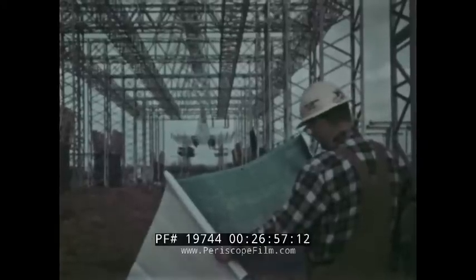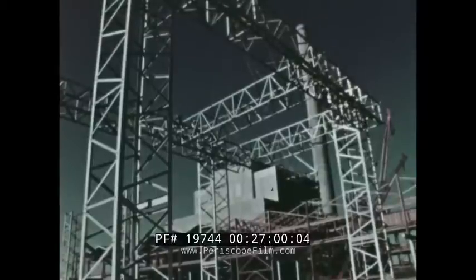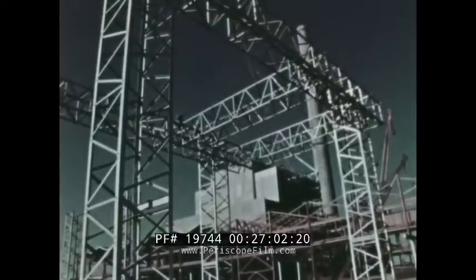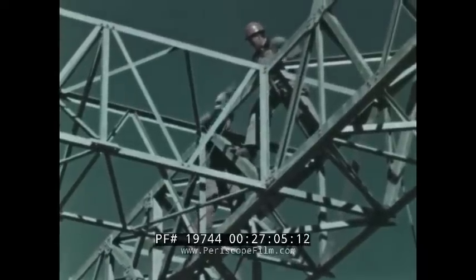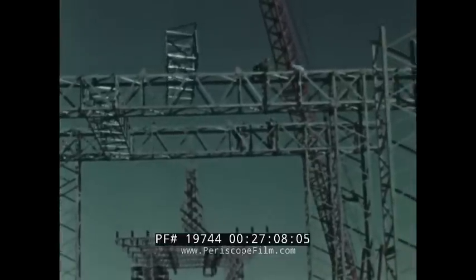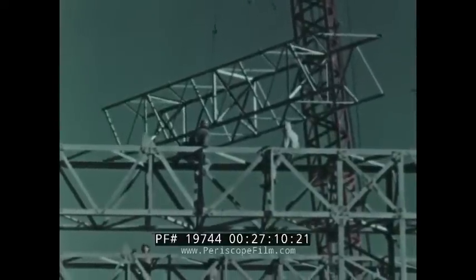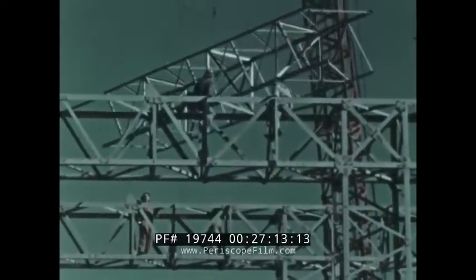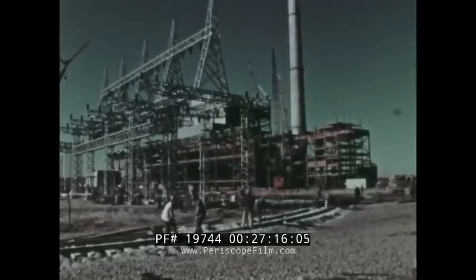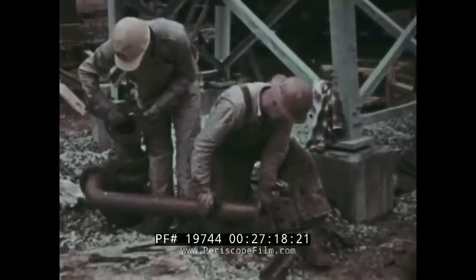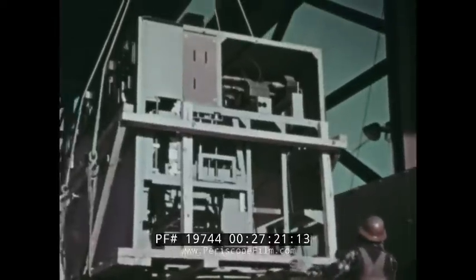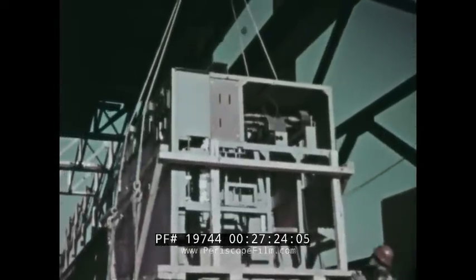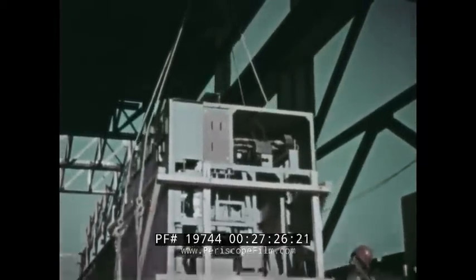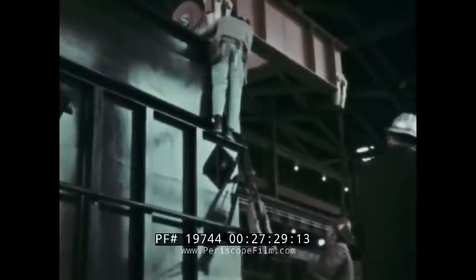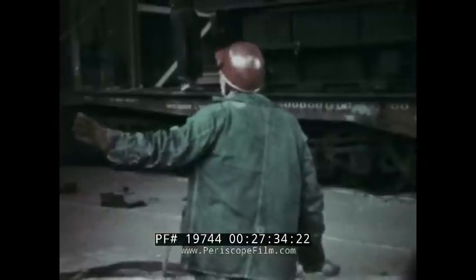From the switchyard, power from Paradise begins its lightning speed journey to the consuming centers. The 24,000-volt output of each generator is carried by bus bar to the outdoor main transformers. Here, the voltage is stepped up to 161,000 volts for transmission to the cities and cooperatives which buy TVA electricity. The main power transformers are rated at 375,000 kilovolt amperes, three-phase, and are cooled by oil pumped through external radiators. Each one weighs over 300 tons.